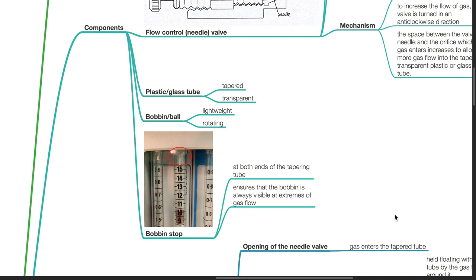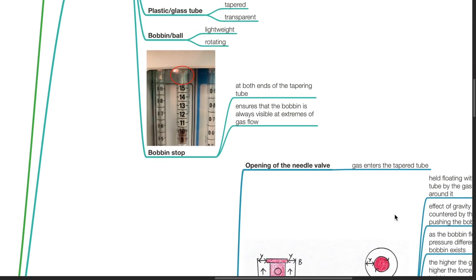The plastic or glass tube is tapered and transparent. The bobbin or ball is lightweight and rotating. There is a bobbin stop at both ends of the tapering tube and ensures that the bobbin is always visible at extremes of gas flow.